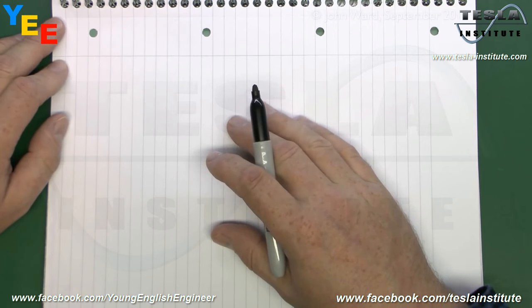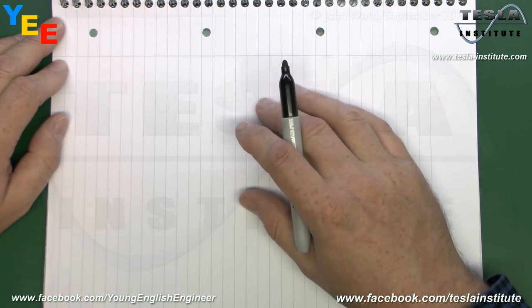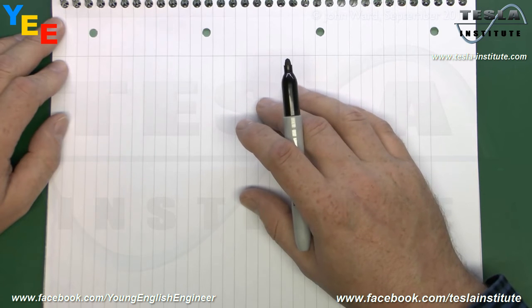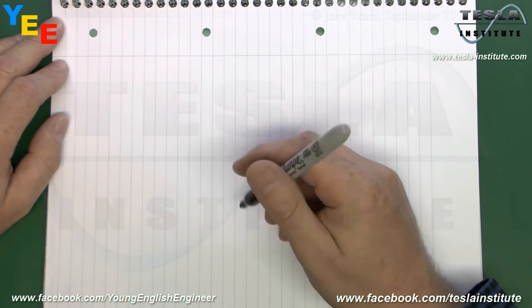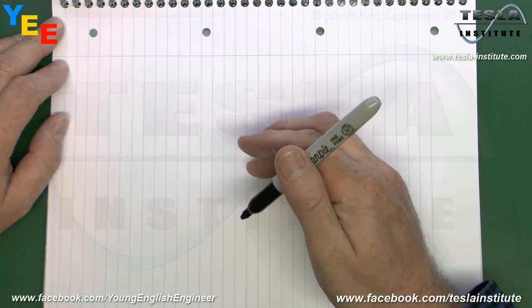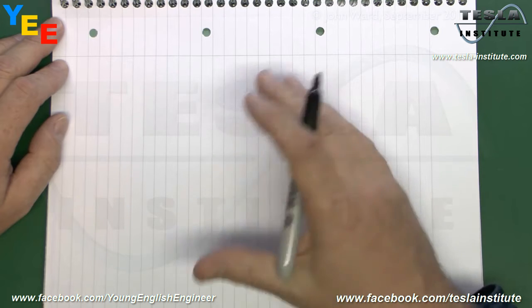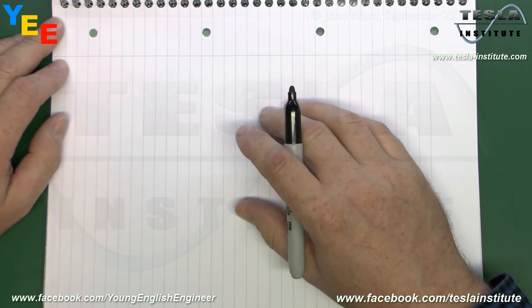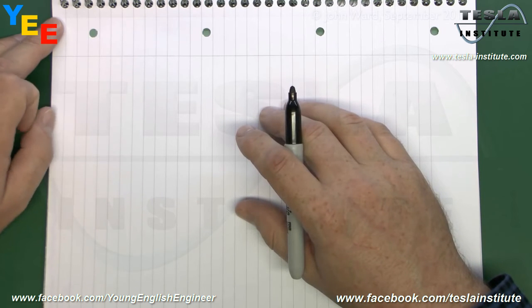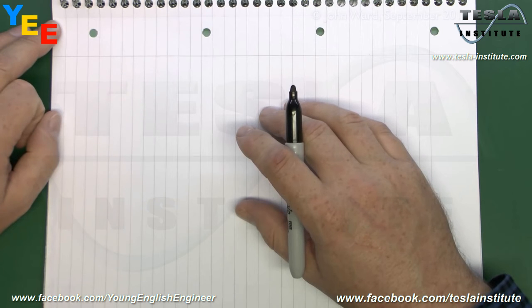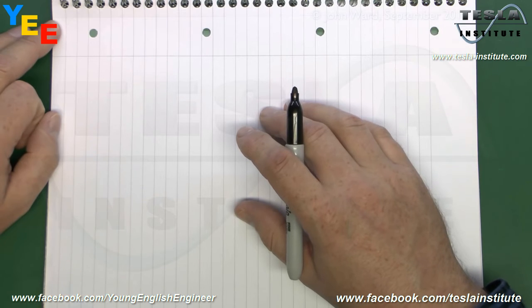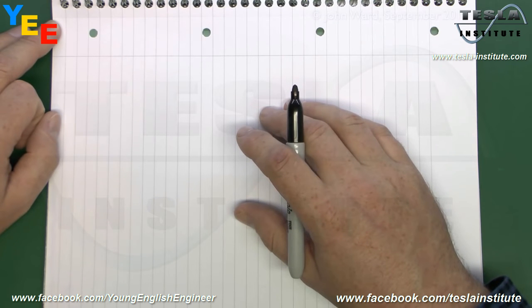And for things like lighting circuits, you do need to go around and remove all of the lamps from the light fittings. And you also need to make sure that the switches for things like lighting circuits are in the on position, because of course if they're not, then you're only going to be actually testing a part of the circuit, and there could be, say, a fault on the cable that goes to a switch. That would of course only show up if that switch was in the on position. And the same for anything else. If you've got permanently wired in equipment, that should ideally be not connected yet, or at least switched off as much as it can be.